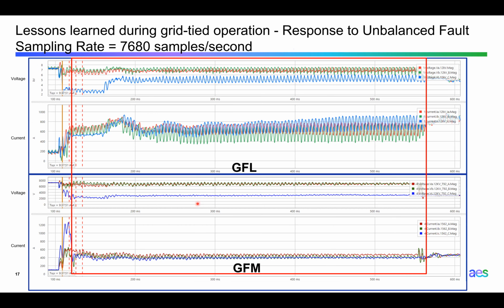Whereas with our grid forming inverters, we are still seeing some oscillation, but not to the same extent as we are in the grid following. So that's great, because that means that our frequency with grid forming shouldn't be necessarily as oscillating as it was with all grid following inverters on the island.